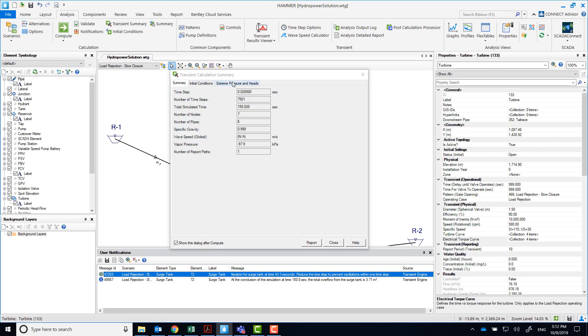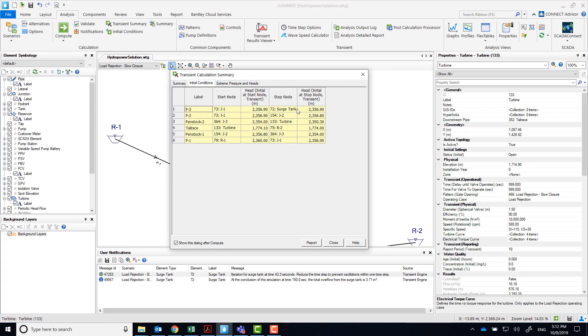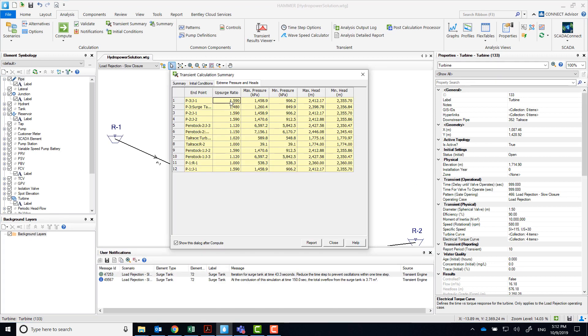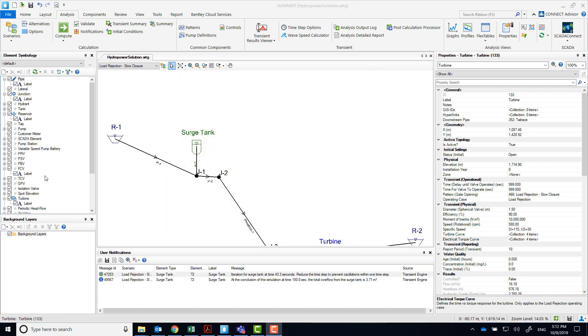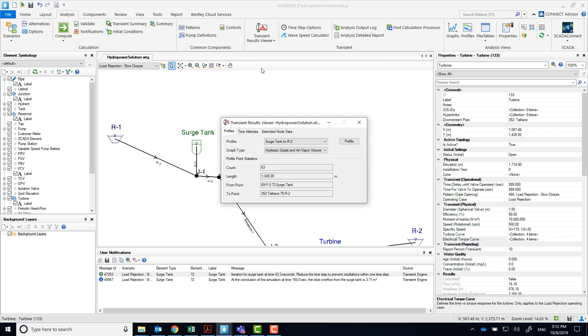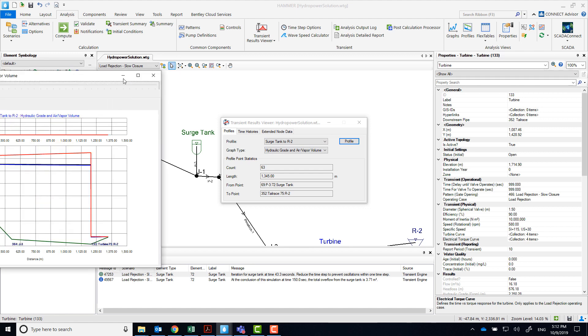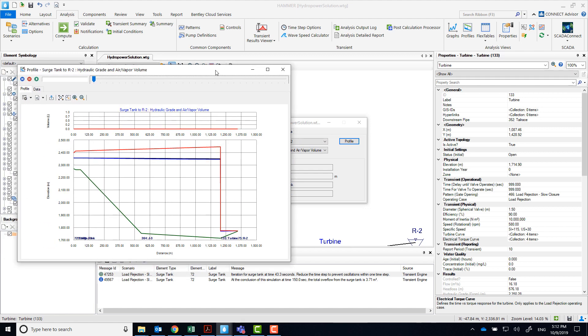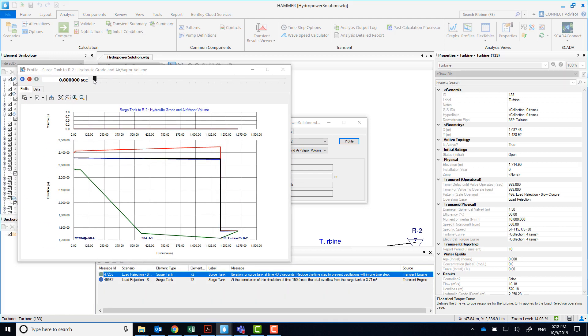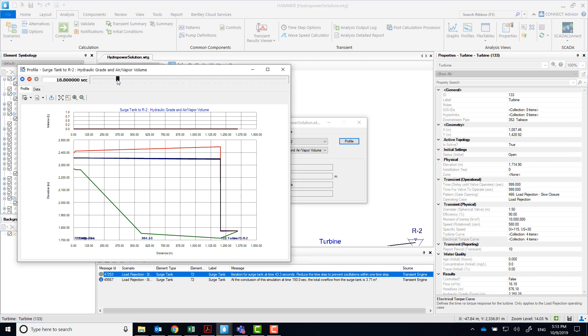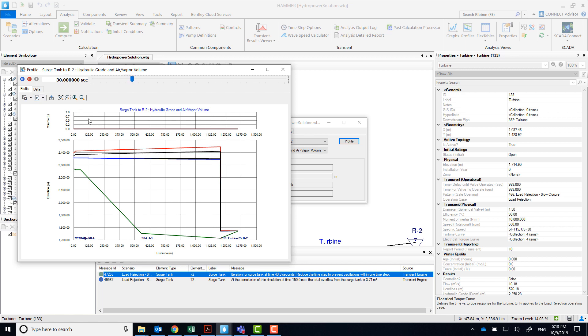Let's look at the extreme pressures and head. You can see that the largest ratio is 1.59, which means the maximum pressure is 1.59 times the steady state pressure. Let's take a look at the profile from the surge tank to the reservoir R2. Notice that in this scenario, there are no vapor pockets forming or collapsing, and the maximum and minimum transient head envelopes are less critical than in the previous scenario.